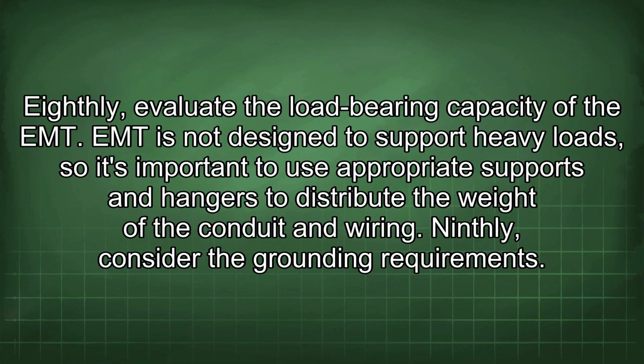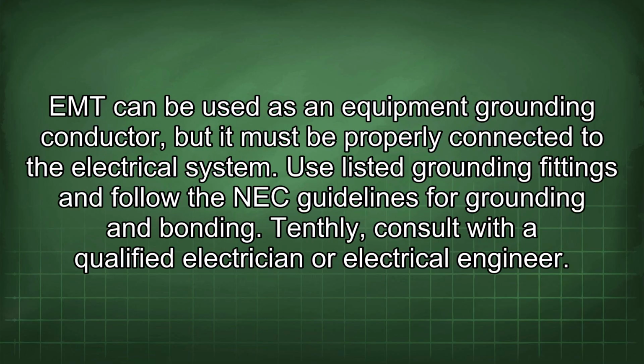Eighthly, evaluate the load-bearing capacity of the EMT. EMT is not designed to support heavy loads, so it's important to use appropriate supports and hangers to distribute the weight of the conduit and wiring. Ninthly, consider the grounding requirements. EMT can be used as an equipment grounding conductor, but it must be properly connected to the electrical system. Use listed grounding fittings and follow the NEC guidelines for grounding and bonding.